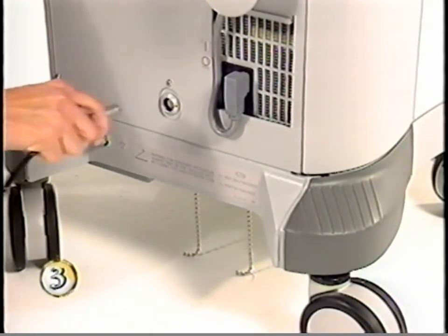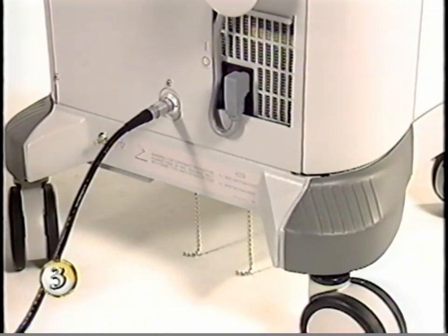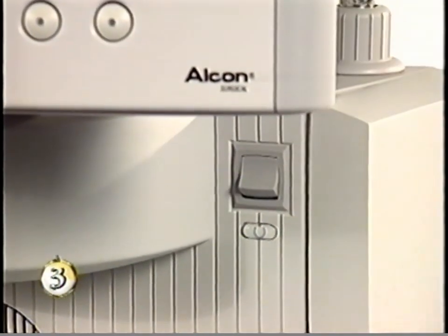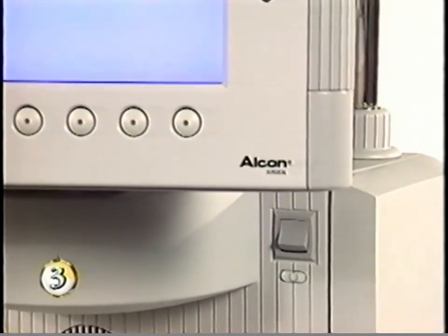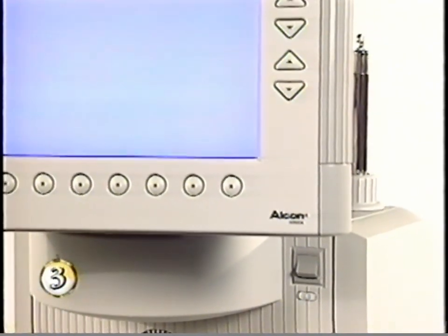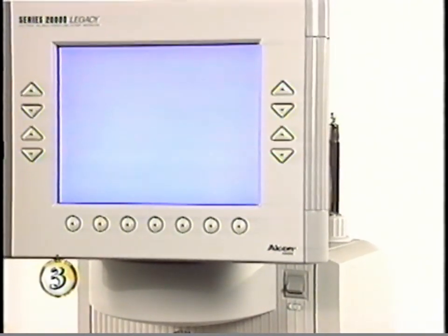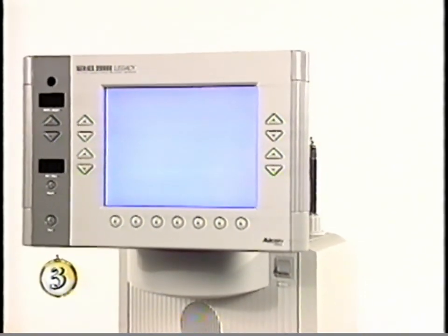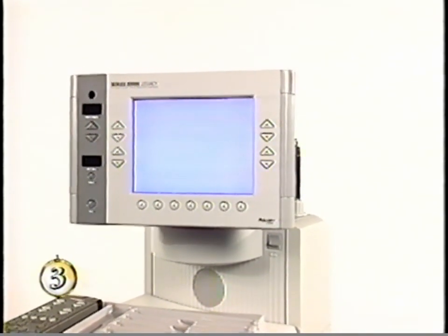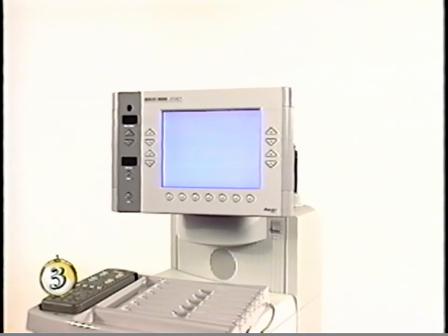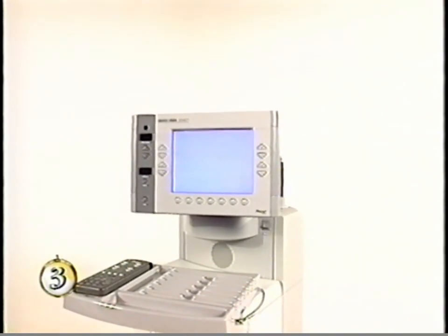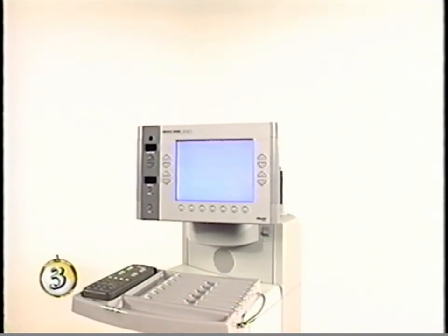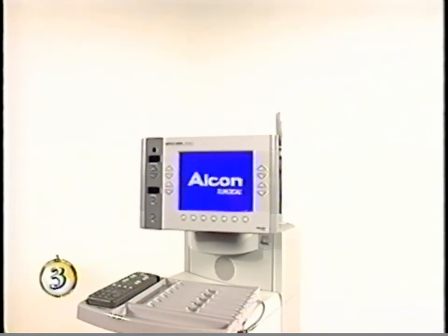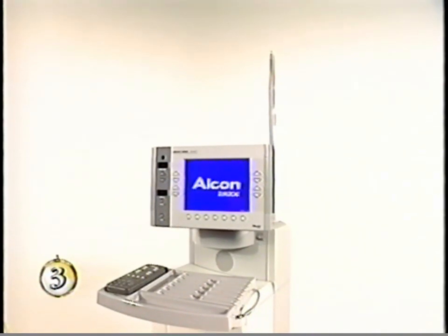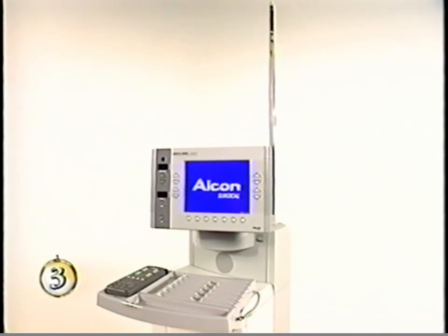To begin both methods, connect the foot switch to the unit at the base of the rear panel. Plug the main power cord into a wall outlet. Always leave the rear panel power switch on. Use the standby power switch on the front panel for normal on-off operation. Once the power switch is turned on, self-test diagnostics will take about 30 seconds. Watch the display for faults or error conditions that may be detected. When these tests are successfully completed, the system enters its default mode, irrigation foot switch, and is ready for setup. Extend the IV pole hook.